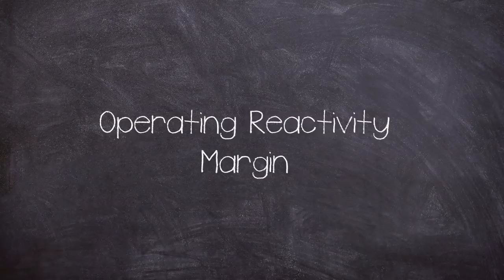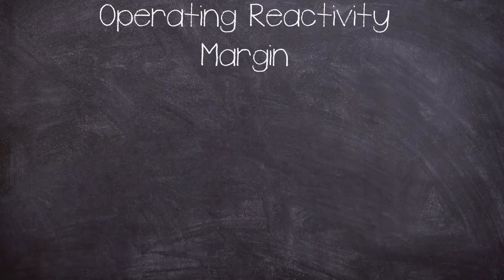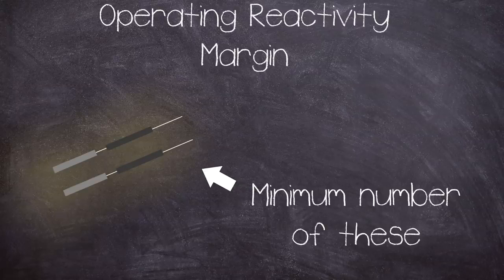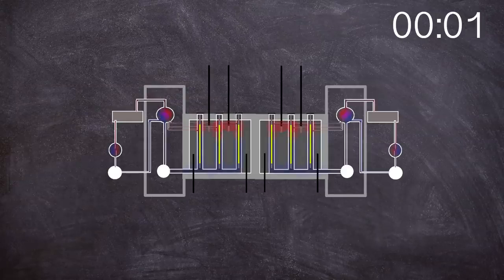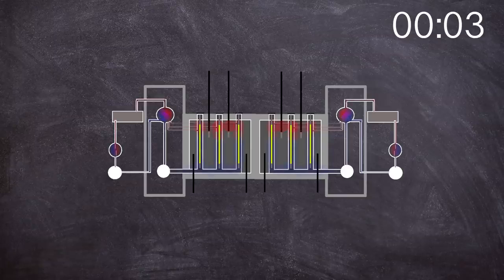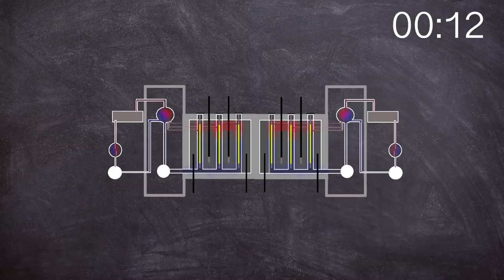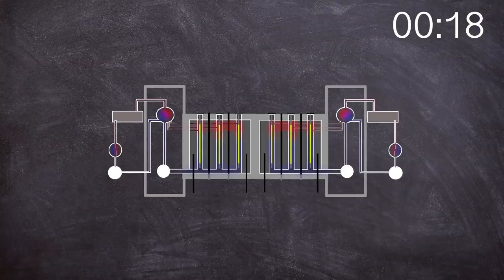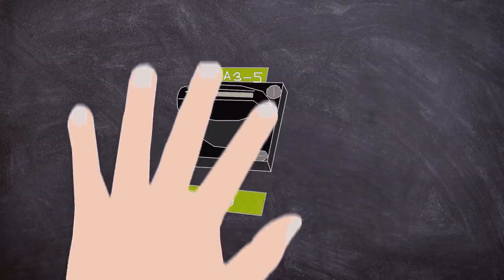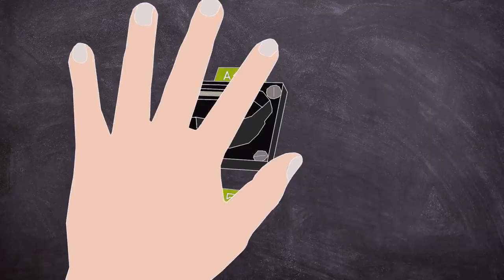The ORM is the number of equivalent control rods of nominal worth remaining in the core. The total time required for a scram or insertion of the emergency control rods into the core when starting from the upper limit stop switches was around 18 seconds. Which was relatively slow but this was due to the size of the control rod channels and the fact that the coolant had to be pushed out of the way. The scram could be initiated by the control system or manually via the AZ5 button.